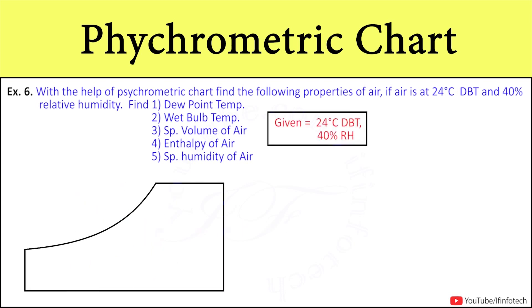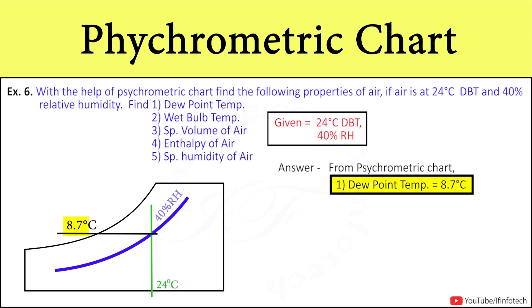So first we will write down the data which has been provided. The given data is air at 24 degrees Celsius dry bulb temperature and 40% relative humidity. And once it is plotted, then we extend this line, we got dew point temperature as 8.7 degrees Celsius.